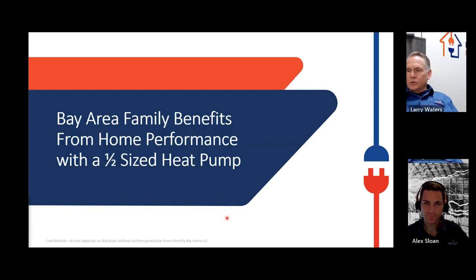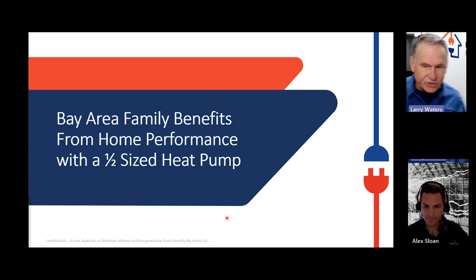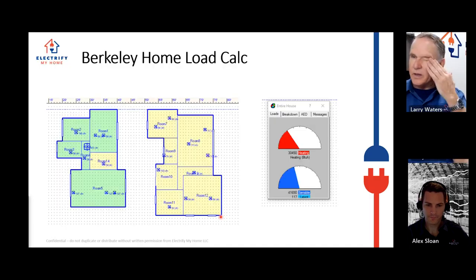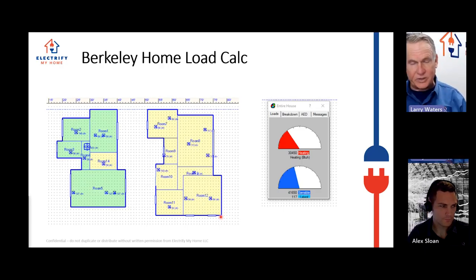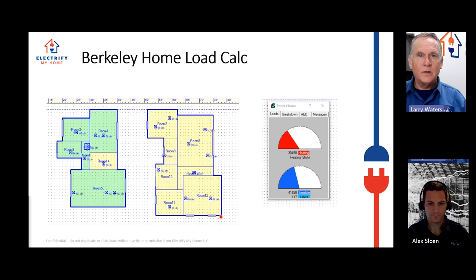Okay. So this is a case study on a house that I pulled. We went through a bunch of them, and I put this case study together. I like the case study itself. It's not a Sacramento case study, which we could have used, a Vacaville, but this one's great because it's got all aspects of the job. It was a house in the Bay Area, but when we do load calculations down there, we find most of the time that the heating load is a little higher than the cooling load. This was a house that had a higher cooling load than heating load.